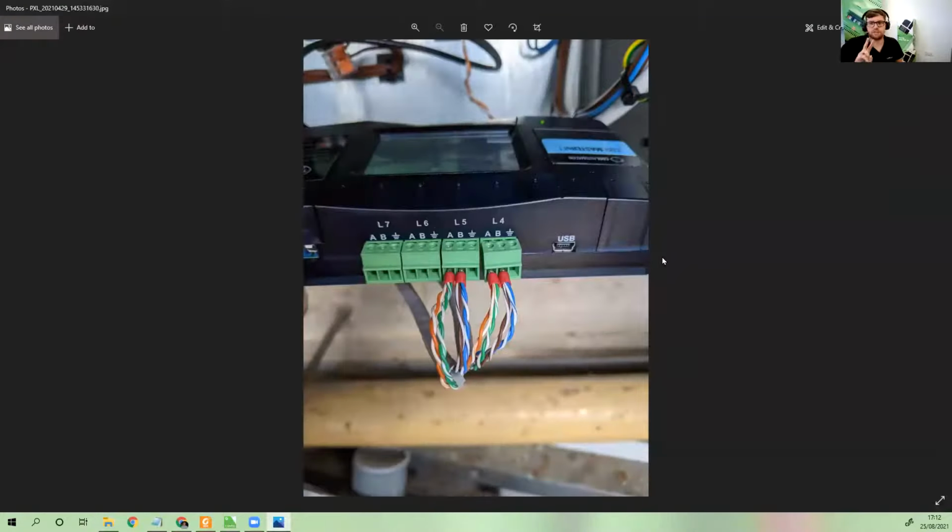As I mentioned, we have 2 outdoor units, hence why I'm using 2 lines. And yes, I did do that wiring. Yes, I'm using Cat5 and I've doubled up the pairs. The reason being is because that is the only cable I had left in the office and I wanted to get us some working aircon. Don't worry, it will be replaced at some point. Probably won't be. So 2 outdoor units, 2 connections from there to R1 and R2 on each outdoor unit.